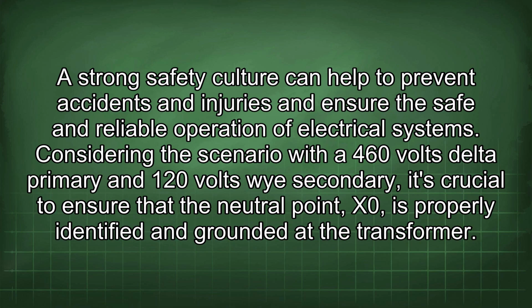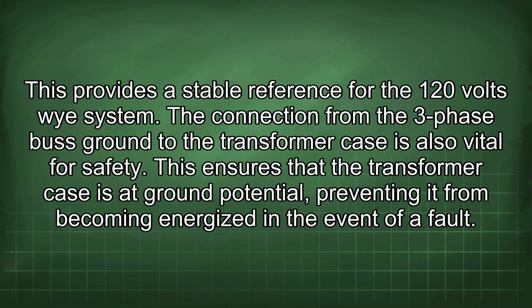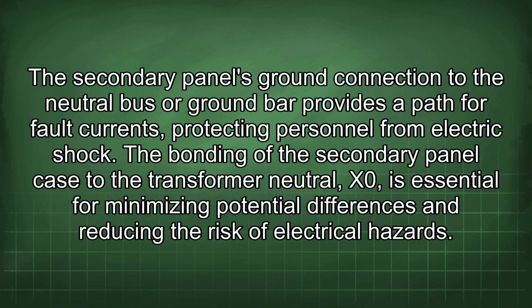electrical systems. Considering the scenario with a 460 volts delta primary and 120 volts Y secondary, it's crucial to ensure that the neutral point, X0, is properly identified and grounded at the transformer. This provides a stable reference for the 120 volts Y system. The connection from the three-phase bus ground to the transformer case is also vital for safety. This ensures that the transformer case is at ground potential, preventing it from becoming energized in the event of a fault. The secondary panel's ground connection to the neutral bus or ground bar provides a path for fault currents, protecting personnel from electric shock. The bonding of the secondary panel case to the transformer neutral, X0, is essential for minimizing potential differences and reducing the risk of electrical hazard.